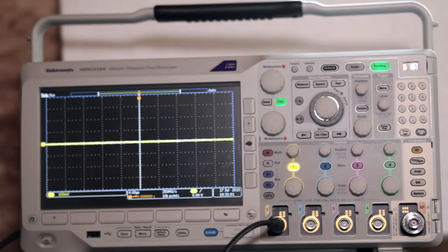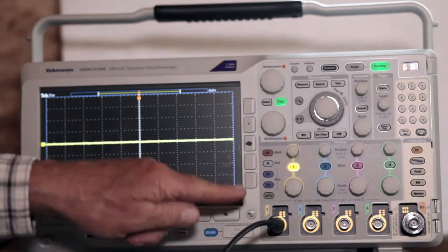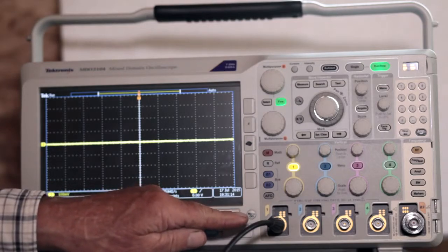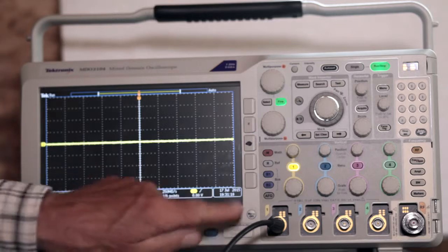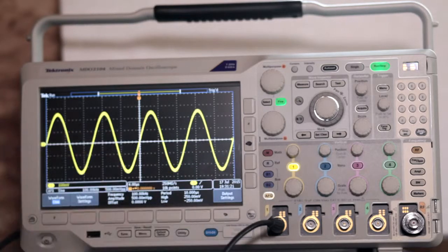To see how this works in the real world, we've connected a BNC cable to the AFG output on the oscilloscope rear panel and hooked the other end of the cable to an analog channel input at the front. Then, after the instrument is booted up, press AFG, the bottom button, in the vertical column to the left of the Channel 1 controls. The first soft key on the left below the display brings up the waveform menu.